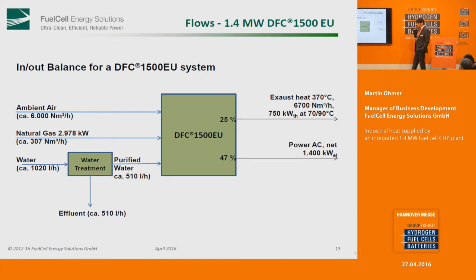The flows, for example, a 1.4 megawatt system. We take ambient air, roughly 6,000 norm cubic meters per hour. We have natural gas, roughly 307 norm cubic meters, and we need some water. Part of the water is used directly for the reformer, for the steam reforming. And the exhaust heat, we have 750 kilowatts with an airflow of 6,700 norm cubic meters, and the power gives 1.4 megawatt net, which is roughly in a year between 11 and 12 gigawatt hours, depending on the hours.